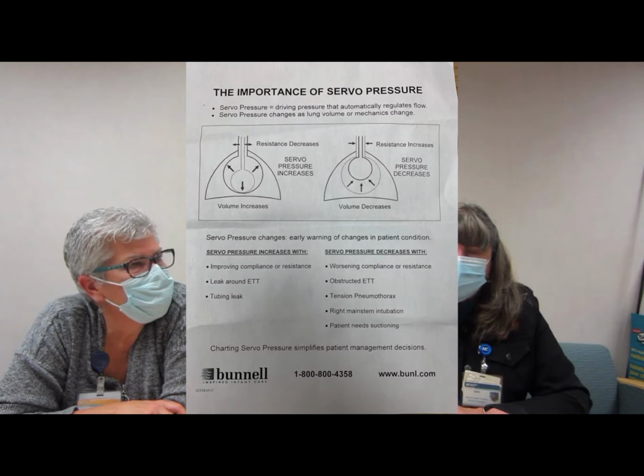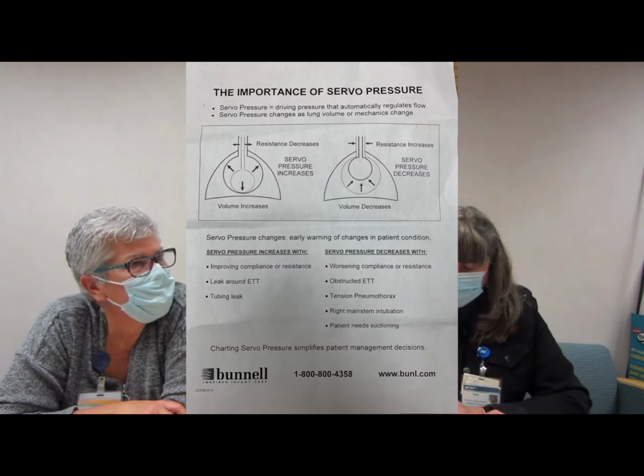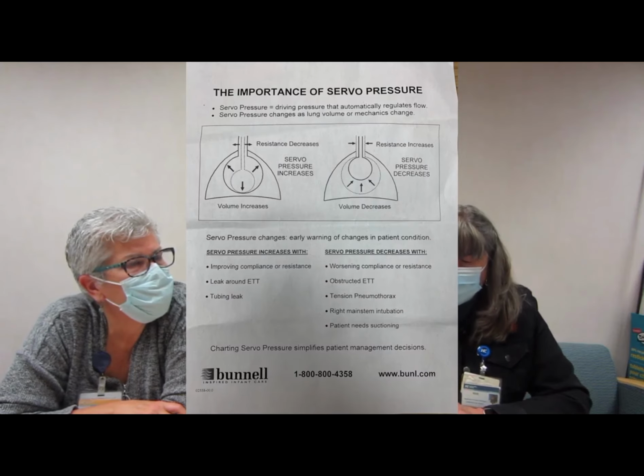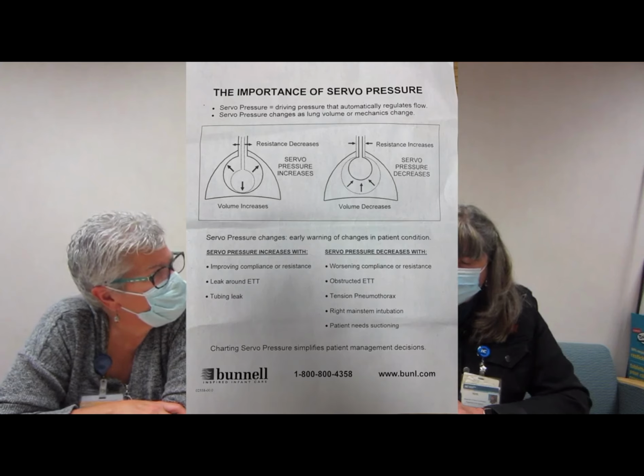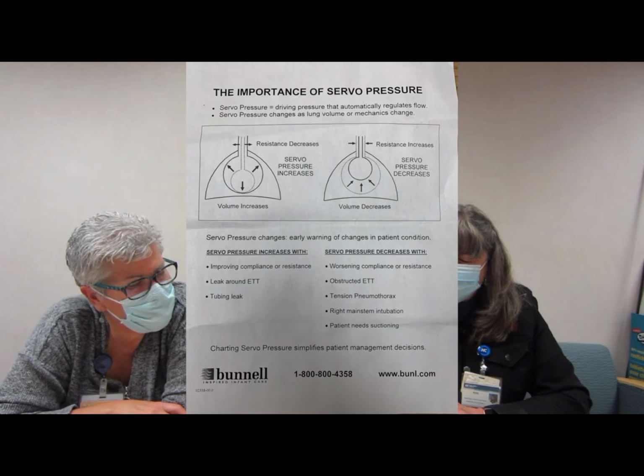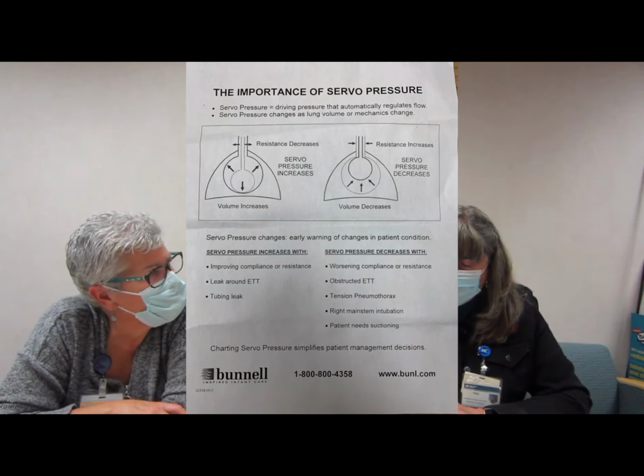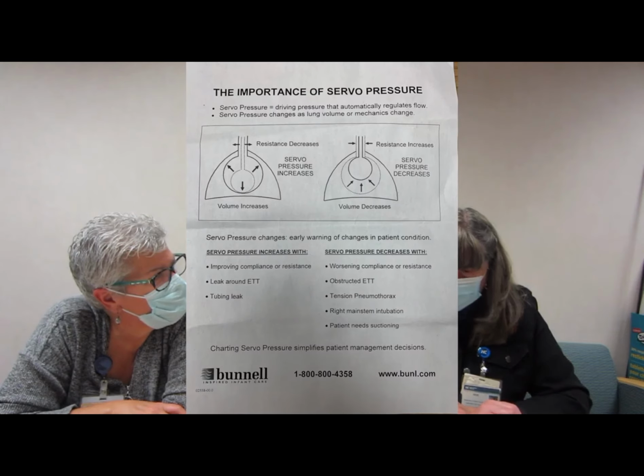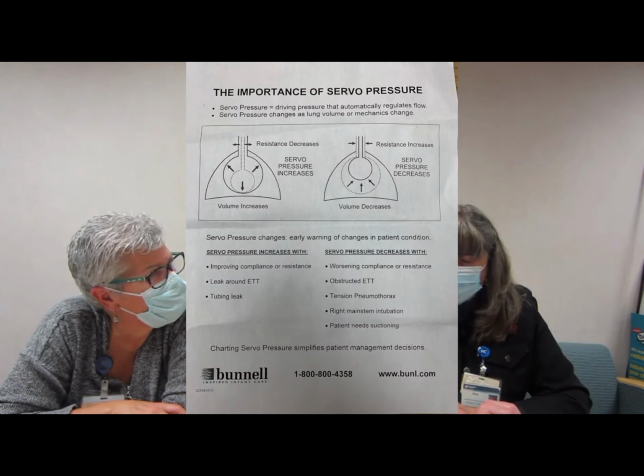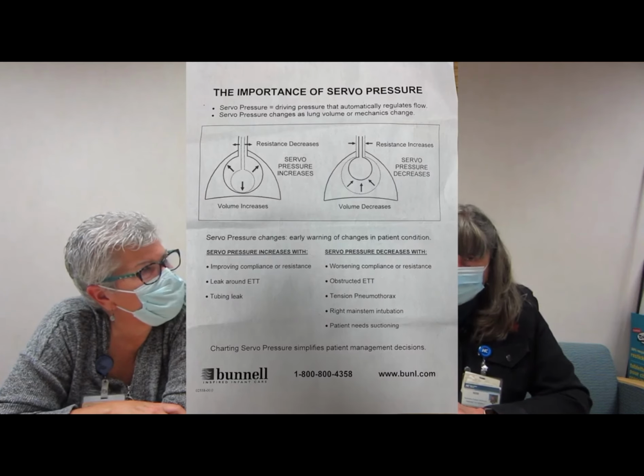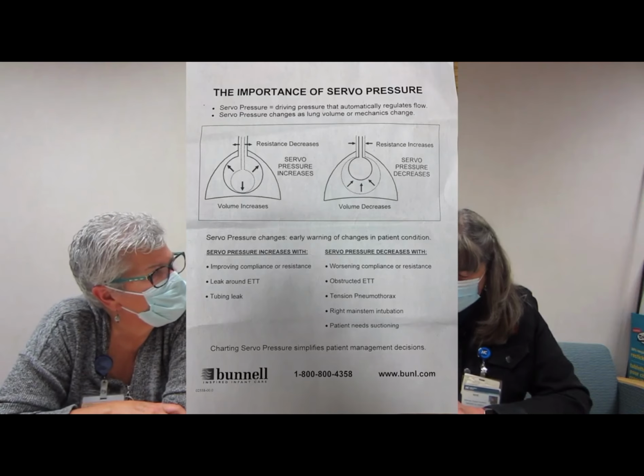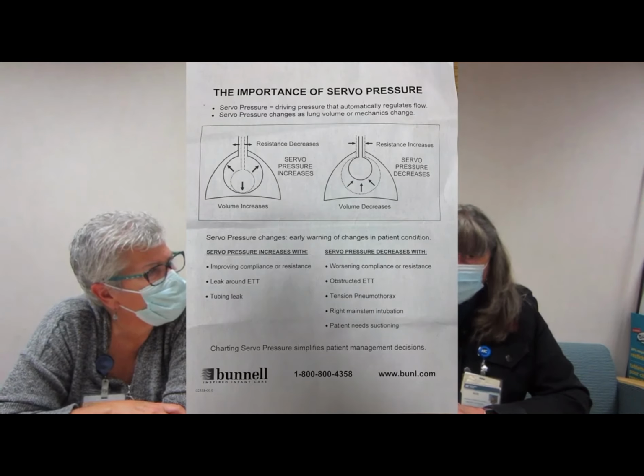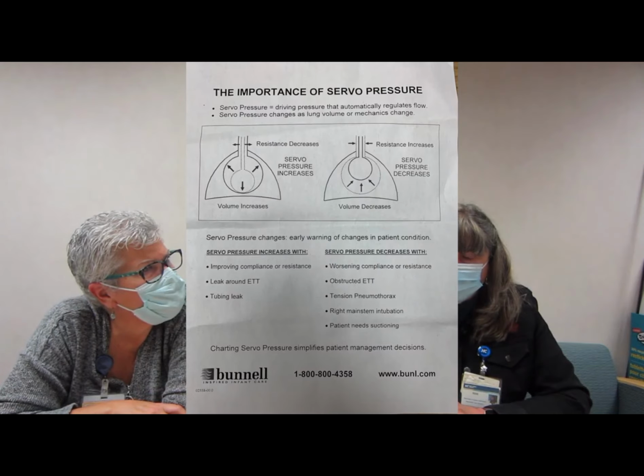So the bigger the space, the higher your servo is going to be. If you have a term baby, your servo pressure may be 2, 3, even 4. If you have a tiny baby, your servo pressure is going to be lower, usually 1 point something. The big thing you have to look for is the change in your servo pressure, because as the lung gets smaller, your servo pressure gets smaller because it's having to ventilate less space. So if you're noticing your servo pressure is getting smaller and your baby's having issues, you probably need to suction your baby. It probably means that there are secretions causing a problem, or it could be your tube is bent, or anything that would make the machine ventilate a smaller space.